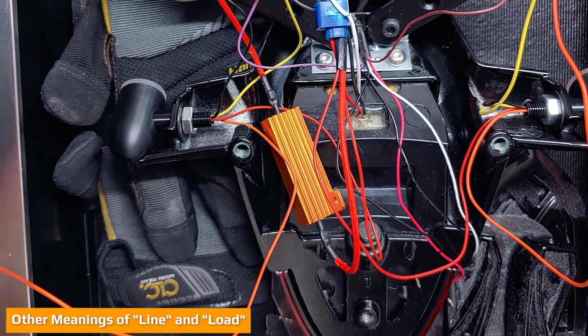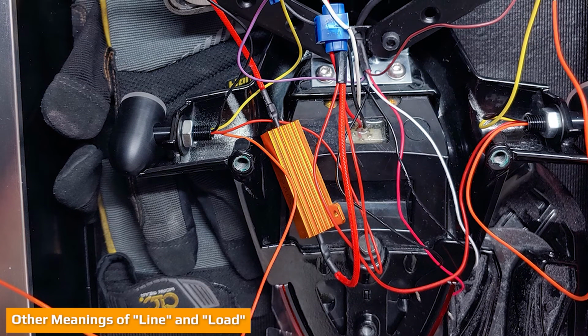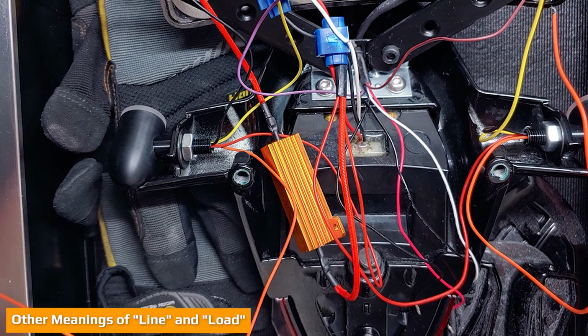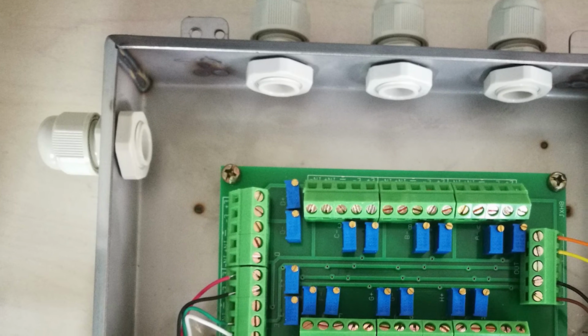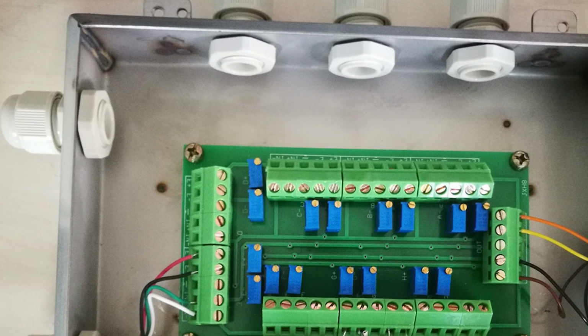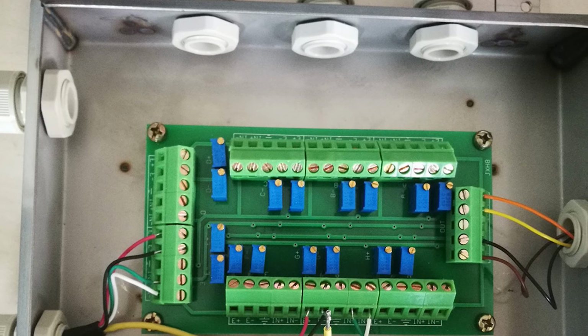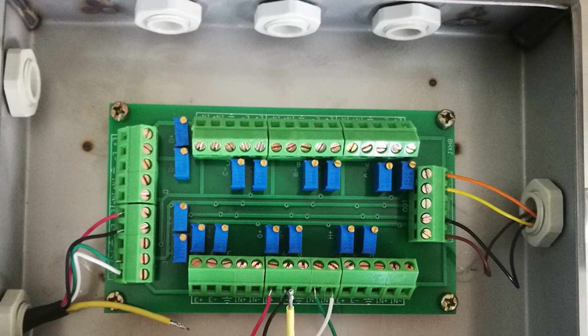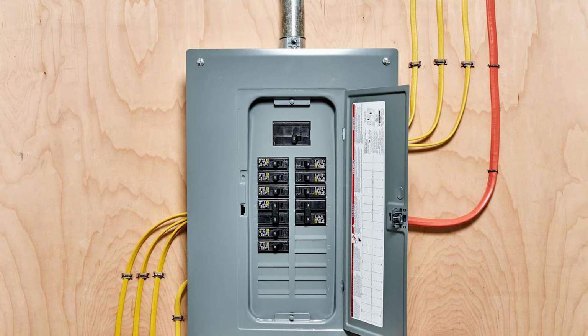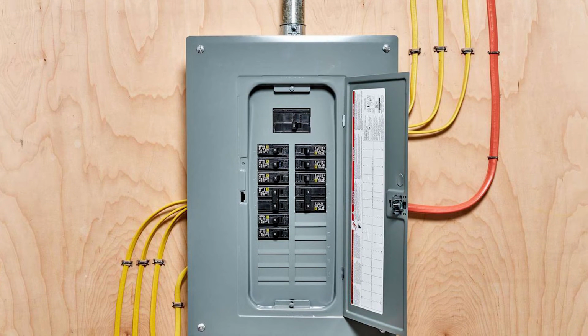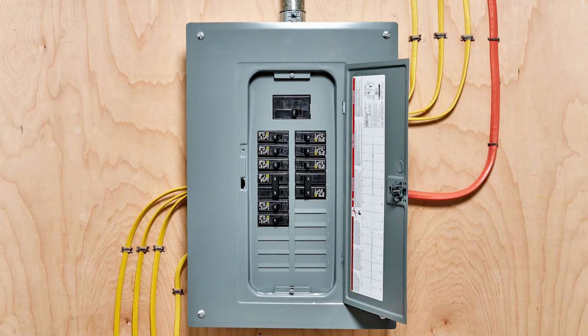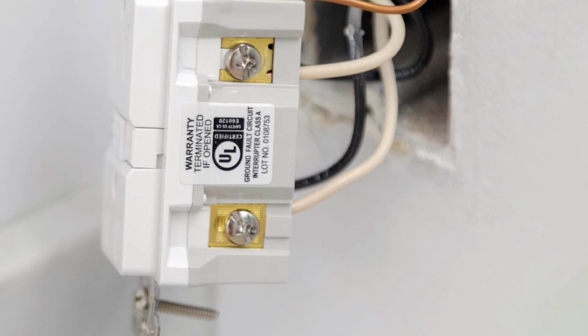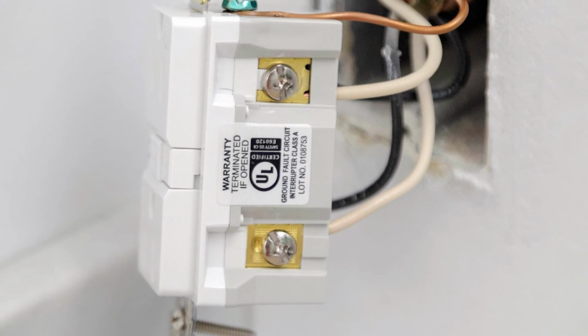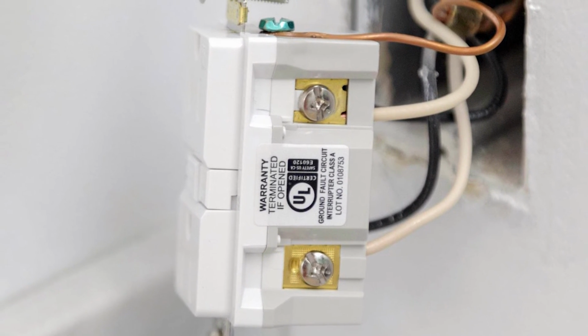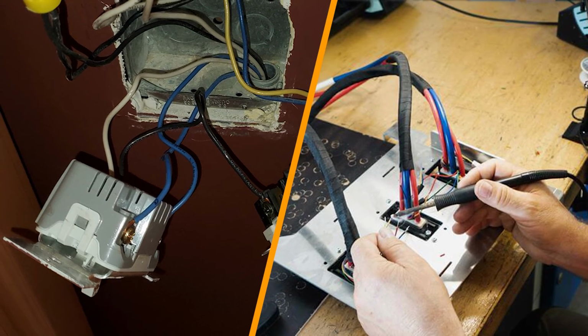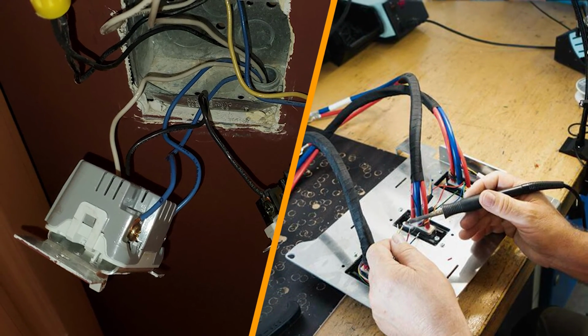When wiring low-voltage circuits, such as those supplying doorbells or landscape lights, line refers to the parts of the circuit that are at full household voltage, usually 120 volts, to distinguish them from the low-voltage wiring and devices that are used after the voltage is stepped down at a transformer. Load is also a general term to describe the electrical demand, or power draw, that a device or appliance places on a circuit. For example, on a lighting circuit, you can add up the maximum wattage of all of the light fixtures on the circuit to calculate the total load, or maximum potential power demand of all the lights.